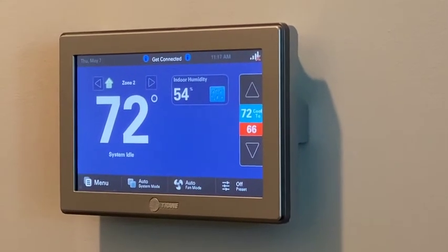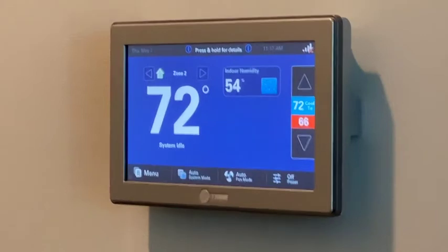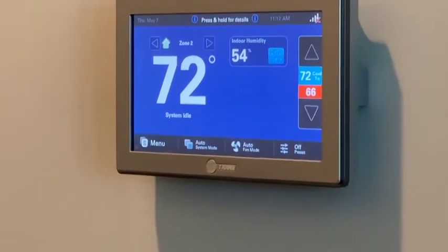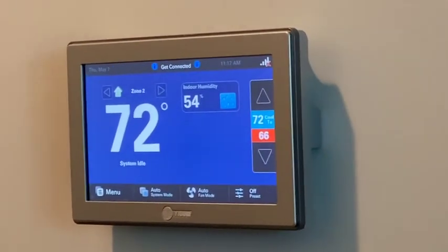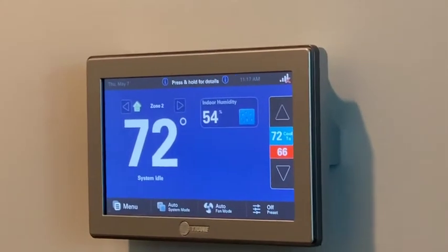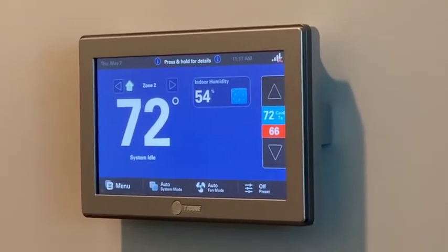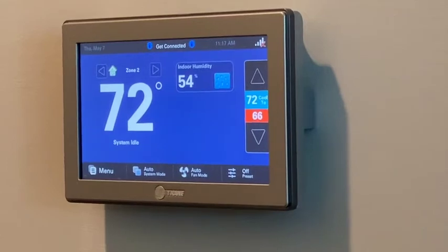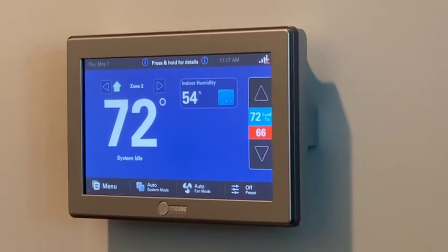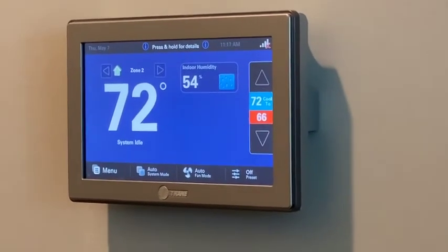If you put this on, let's say your house, you put gas in your house and you wanted to put this thermostat on, now we have to install what's called a relay panel to make this particular thermostat work. Now they do make a smaller one. It's a smaller version of this that will work with any 24 volt standard heating and air system.